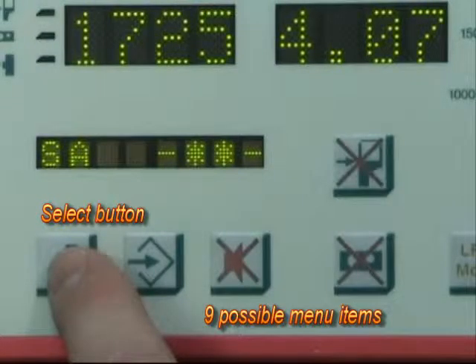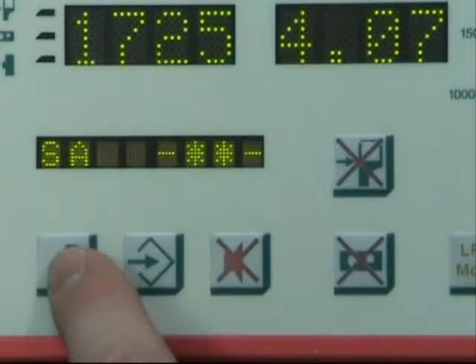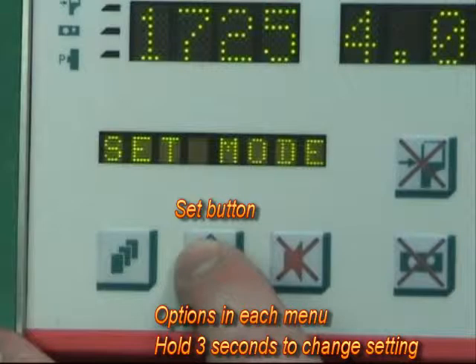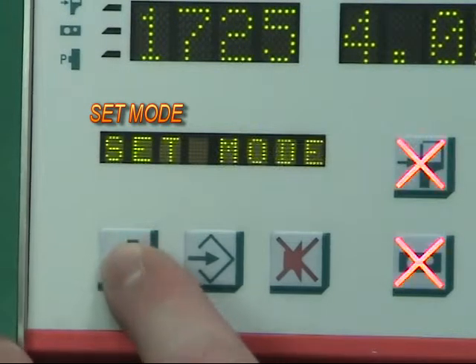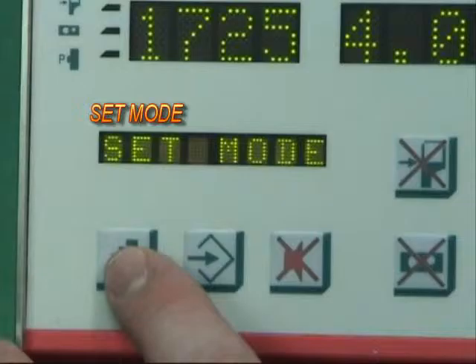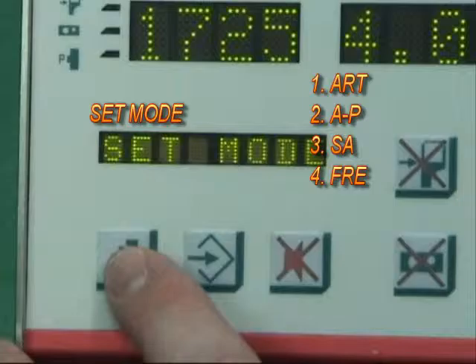Pressing the Select button on the Rotoflow control panel allows you to scroll through 9 possible menu items. Pressing the Set button scrolls through the available options in each menu, and holding down the Set button for 3 seconds changes the setting. To exit the menu, press any other button on the control panel. The Set Mode menu item selects the mode of operation. The Rotoflow pump has 4 operational modes, defined primarily by alarms that influence the pump. These include arterial and arterial pulse, standalone, and free.